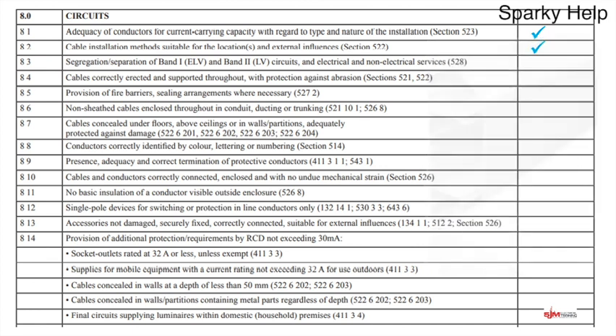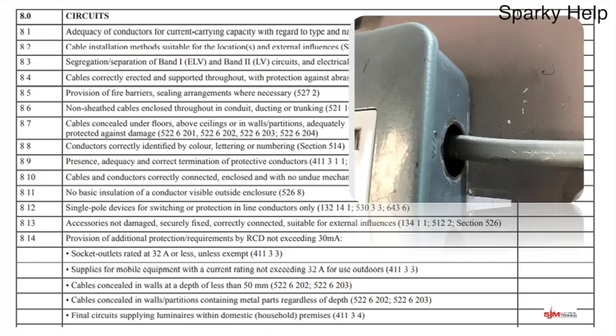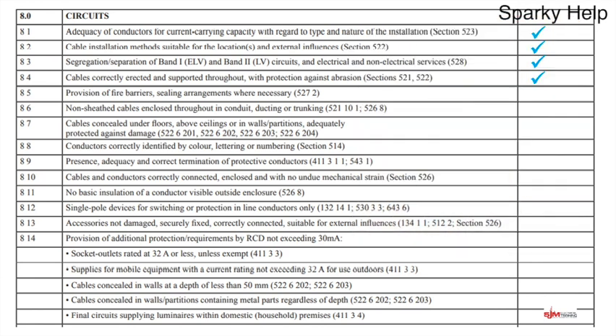Cables correctly erected and supported throughout with protection against abrasion — that does exactly what it says on the tin. Is all the equipment installed correctly, supported, and protected against abrasion? If we look here going into an accessory there's no grommet — it probably fails on the IP rating as you could probably get your finger in there — that sort of thing you'd need to pick up on. But let's go for a tick.